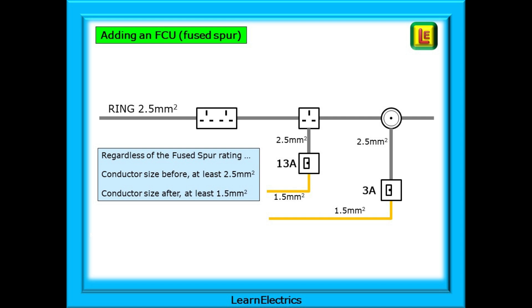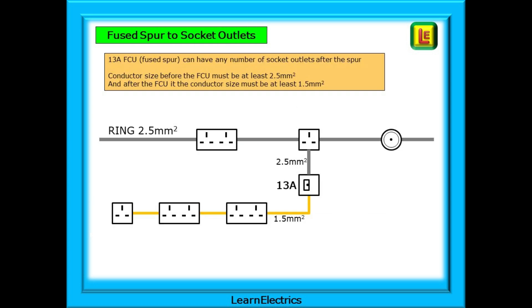Just to reiterate this important rule on cable size: regardless of the fused spur rating, conductor size before the FCU must be at least 2.5mm and conductor sizes after at least 1.5mm. If we are installing a fused spur to supply socket outlets, then we use a 13 amp FCU or fused spur and now it can have any number of socket outlets after the spur. Once again, the conductor size before the FCU must be at least 2.5mm and after the FCU, the conductor size must be at least 1.5mm.